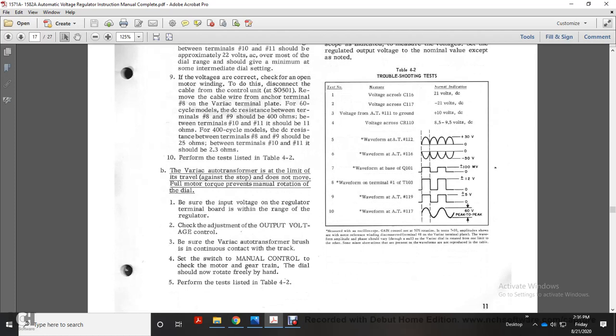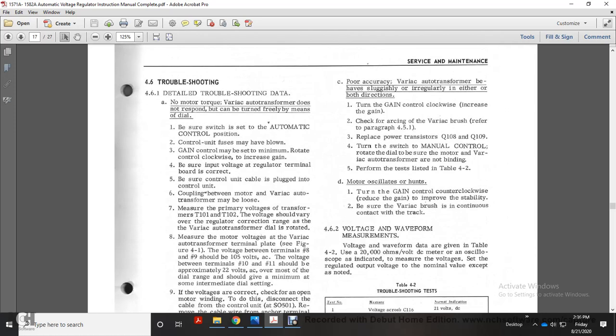B. The Variac autotransformer is at the limit of the travel against the stop. It does not move with the full motor torque. Prevents motor rotation over the dial. Be sure for the input voltage regulator terminal board within the range of the volt regulator. Check for the adjustment of the output voltage control. Be sure for the Variac autotransformer brushes the continuous contact with the track. Set switch manual control to check with the motors with the gear trailing with the dial should now rotate freely by hand. Perform test listed in table 4-2.